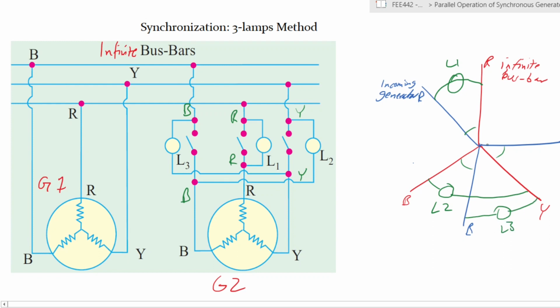So you have lamp 3 connected in between those. Of course, the phasor diagram is a bit counterintuitive, but it should show us what we want to see. This L2 is not supposed to be here. L2 is between yellow of infinite and blue of the incomer, so this is actually L2. Sorry about that. And then you have L3, which is connected between blue of the infinite and yellow of the incomer. Okay, so it's actually like that. Fine. So you have those 3 lamps connected in that phase sequence.